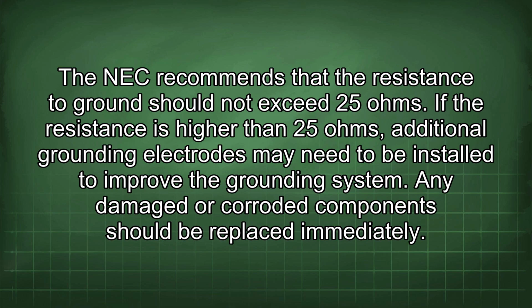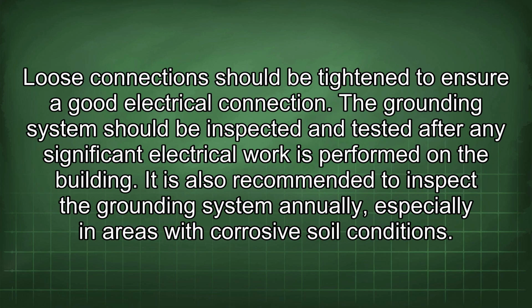The NEC recommends that the resistance to ground should not exceed 25 ohms. If the resistance is higher than 25 ohms, additional grounding electrodes may need to be installed to improve the grounding system. Any damaged or corroded components should be replaced immediately. Loose connections should be tightened to ensure a good electrical connection. The grounding system should be inspected and tested after any significant electrical work is performed on the building. It is also recommended to inspect the grounding system annually, especially in areas with corrosive soil conditions.